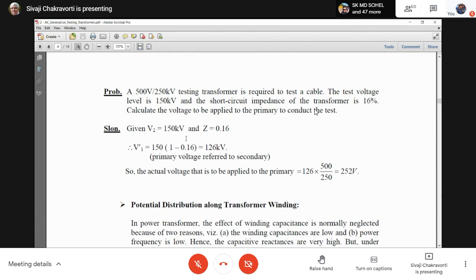So in our case, V2 is 150 kV. That should be the terminal voltage. Z is 16%, that means 0.16. So the transformer voltage referred to the high voltage side is 150 into (1 minus Z), so it comes to 126 kV. This is the primary voltage referred to the secondary, that means on the high voltage side. Now when I refer to the primary, that is the low voltage side, simply by the turns ratio, it comes to 252 volts. So if I apply 252 volts to the primary, I get 150 kV in the secondary. This is something we should know when we perform such tests in our lab.